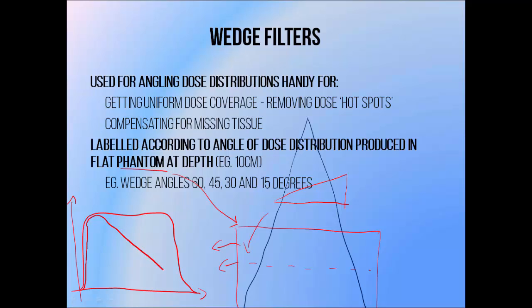In a flat phantom, this results in an angled dose distribution. We can create dose distributions at different angles — normally 60, 45, 30, and 15 degrees in clinical practice. These angles are defined as the angle between the dose distribution on the central axis and the horizontal plane in a profile measured at depth in a flat phantom, normally at a depth of 10 cm.